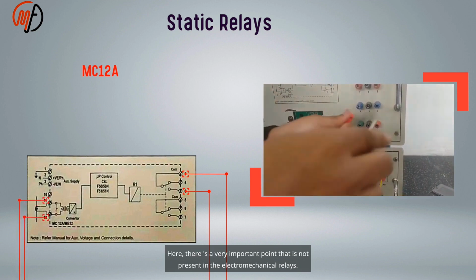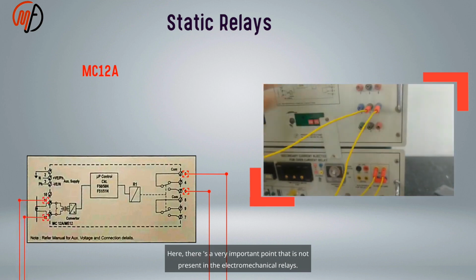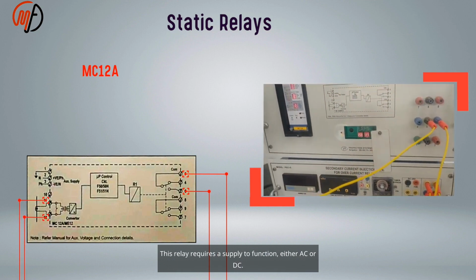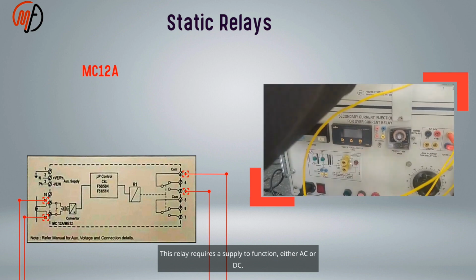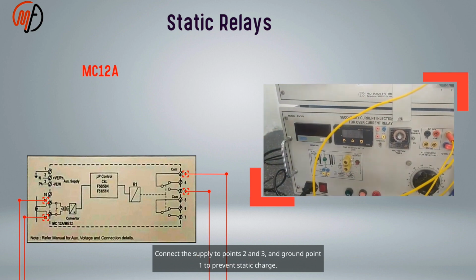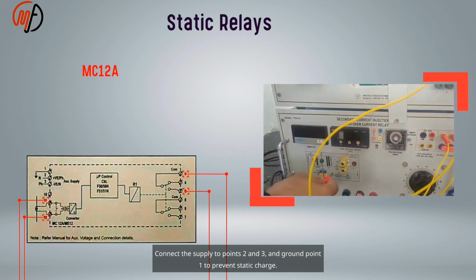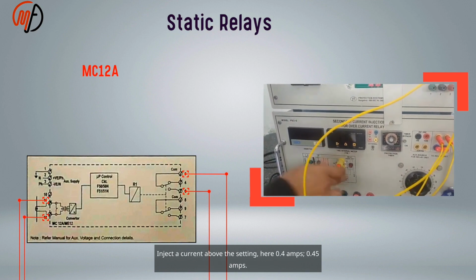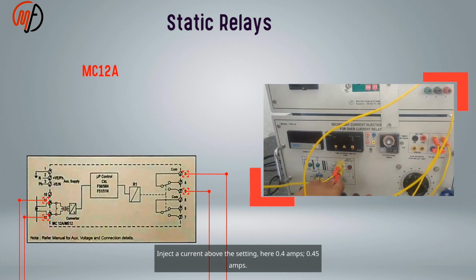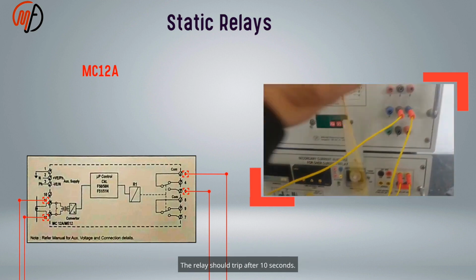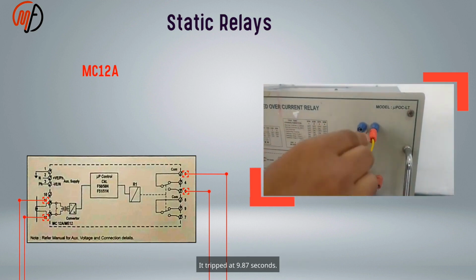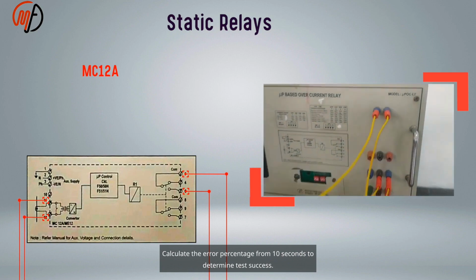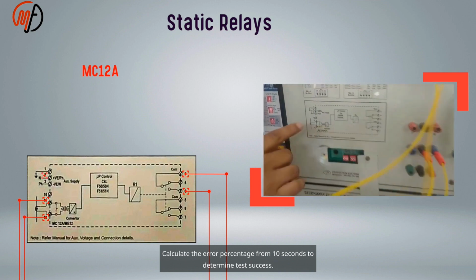Here, there's a very important point that is not present in the electromechanical relays. This relay requires a supply to function, either AC or DC. Connect the supply, points 2 and 3, and ground point 1 to prevent static charge. Inject a current above the setting, here 0.4 amps, 0.45 amps. The relay should trip after 10 seconds. It tripped at 9.87 seconds. Calculate the error percentage from 10 seconds to determine test success.